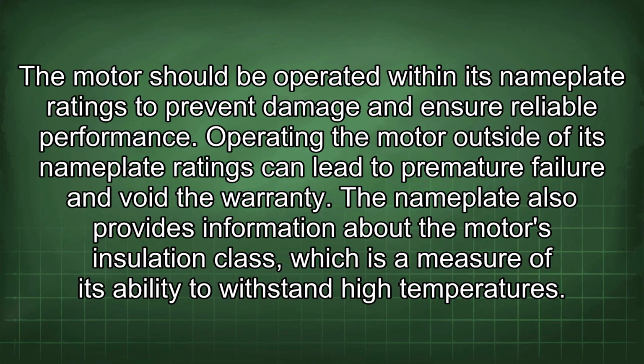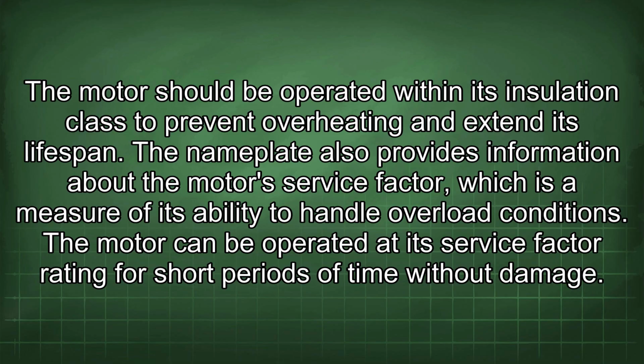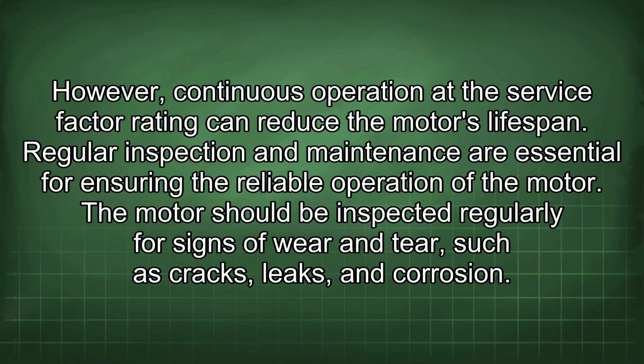The nameplate also provides information about the motor's insulation class, which is a measure of its ability to withstand high temperatures. The motor should be operated within its insulation class to prevent overheating and extend its lifespan. The nameplate also provides information about the motor's service factor, which is a measure of its ability to handle overload conditions. The motor can be operated at its service factor rating for short periods of time without damage. However, continuous operation at the service factor rating can reduce the motor's lifespan.